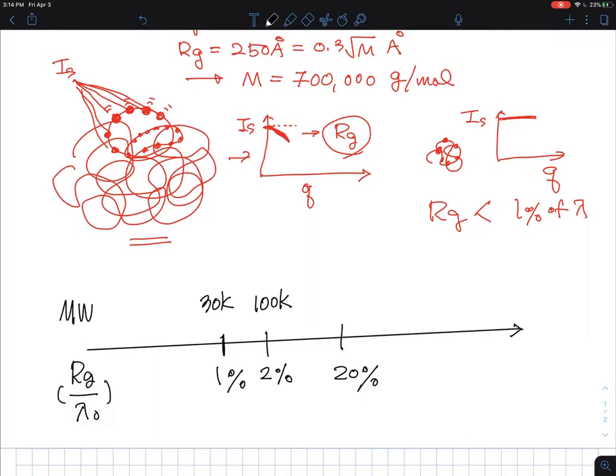If one of your friends says, hey, you have a light scattering equipment, I made a polymer sample, you know, the molecular weight is not so high, but I really want to measure the size of the polymer. GPC says that the weight average molecular weight is, for example, like 30K or 10K. Can I measure the size using the light scattering? You just say no, you can't do that because the size is so small compared to the wavelength of the light, there's not enough reduction as changing the scattering angle. So although you have a super-duper light scattering instrument, you cannot really see the changes.